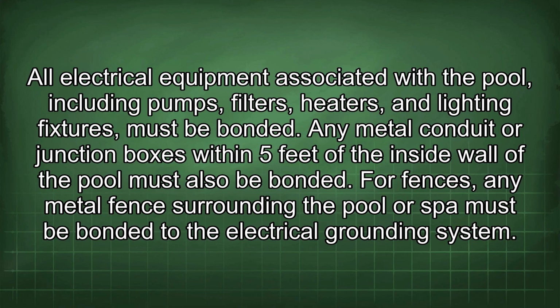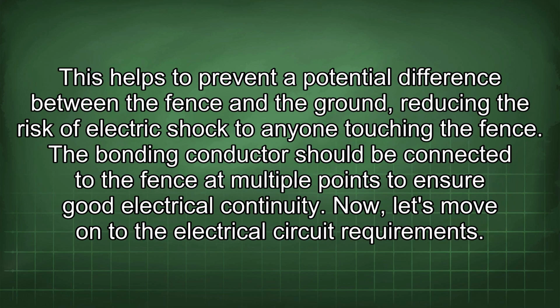For fences, any metal fence surrounding the pool or spa must be bonded to the electrical grounding system. This helps to prevent a potential difference between the fence and the ground, reducing the risk of electric shock to anyone touching the fence. The bonding conductor should be connected to the fence at multiple points to ensure good electrical continuity. Now let's move on to the electrical circuit requirements.